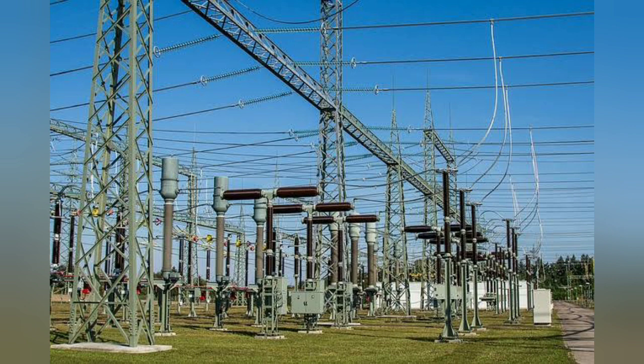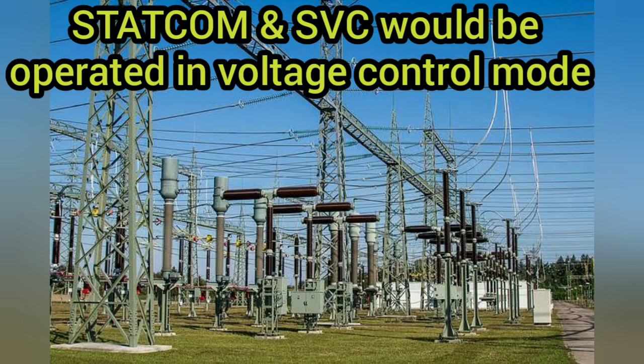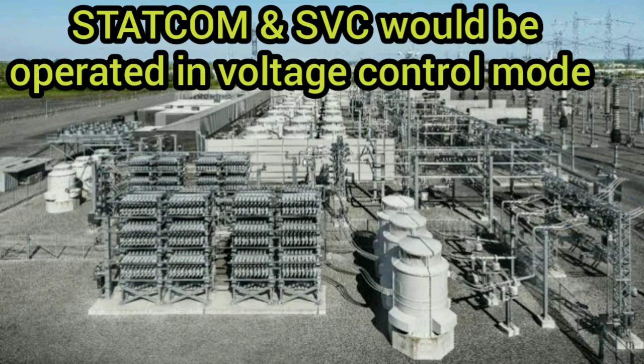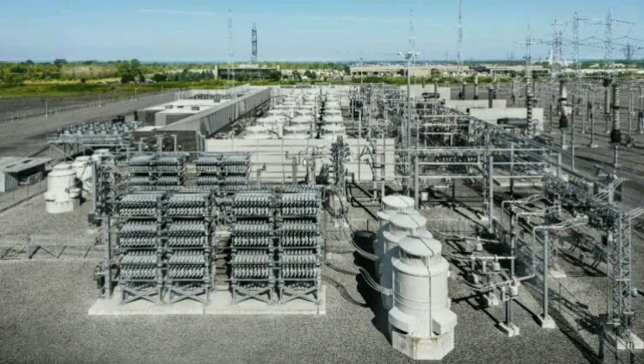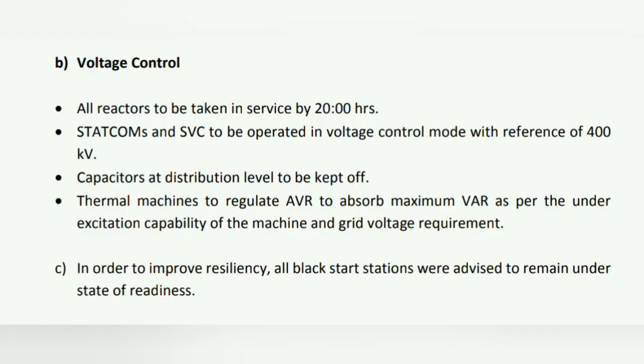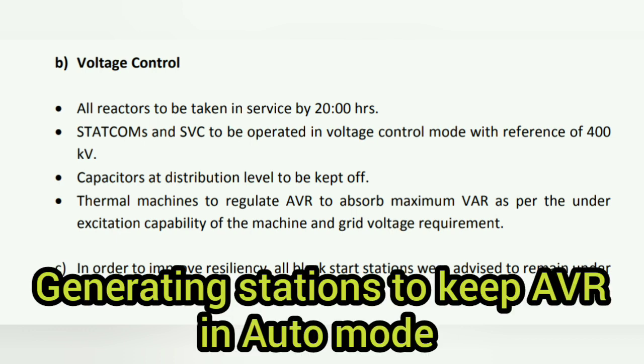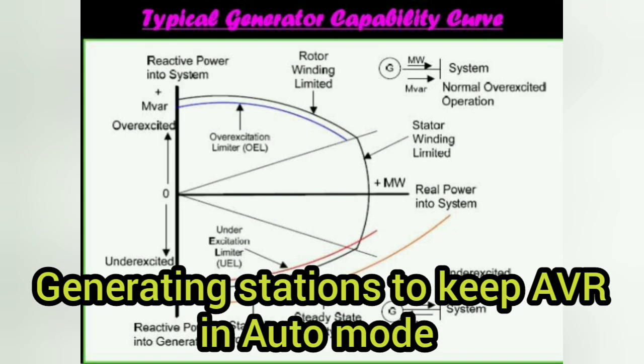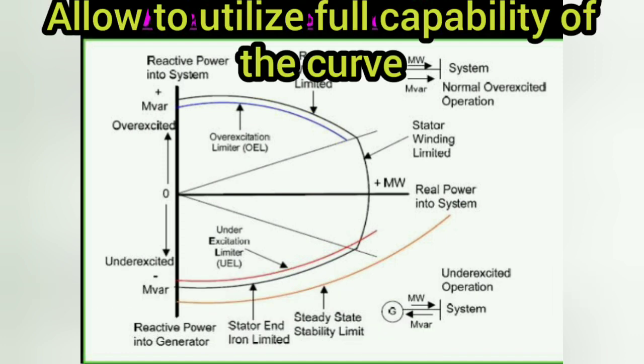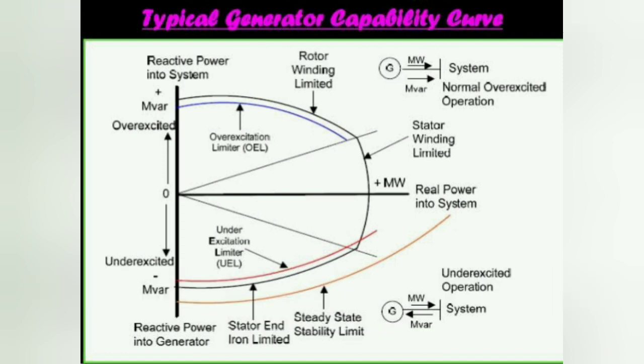All such lines could be opened before the event, and all the STATCOMs and SVCs would be operated in voltage control mode with reference voltage being 1 pu. All generating stations were to keep voltage regulators in automatic mode and allow utilization of the full capability curve of the unit during the event. With lower active power generation at generating units, the increased reactive power capability needed to be utilized as dynamic reactive reserve in the system.